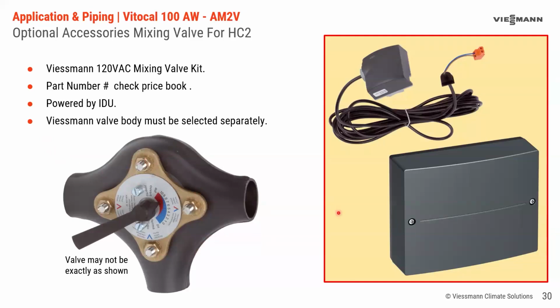And the reason why we do that is this is standard for every mixing valve we're going to use, but the valve could be a 3/4 inch, could be a 1 inch, could be an 1.5 inches. We don't know what valve size you're going to want, so that's why you order the valve body separately. This motor will fit on any of the valve sizes that we supply.